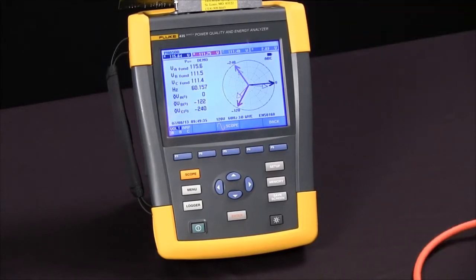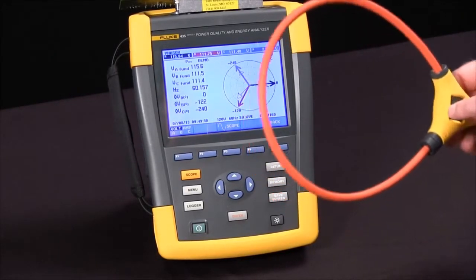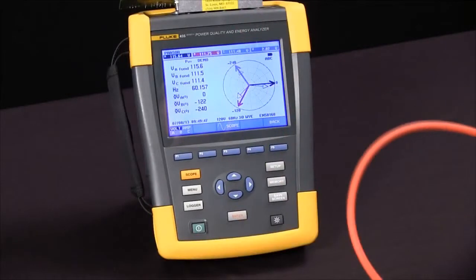The way to see when you have a difference, or if you see you have to make a correction for the current clamp, the way to do that is look for an arrow on the inside of the CT that should be pointed towards the load. Once you've done that, you should be properly configured for your Fluke 435 power connection.